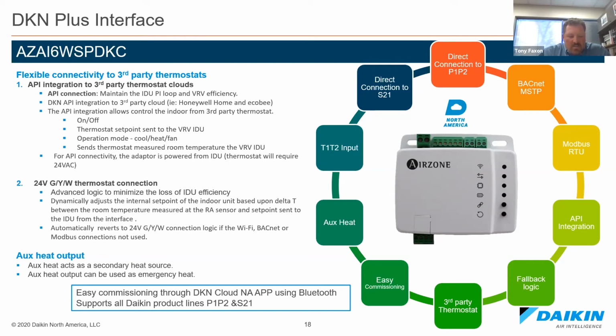So you lost significant efficiency. So with the DKN Plus interface, Daikin has built into the interface the software to take that on-off signal and convert it back to a modulating signal for the expansion valve. In addition to this feature, the interface can communicate to BACnet, Modbus. It can run a secondary auxiliary heat. And again, commissioning is very easy with a Bluetooth app.